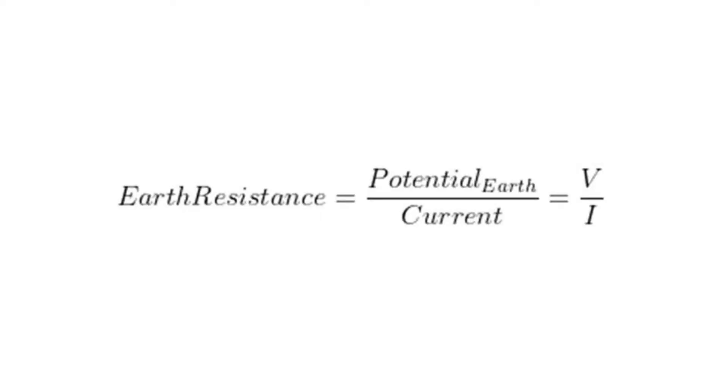When we talk about Earth resistance, we mean the resistance of the Earth electrode where the current flows into the ground. The Earth electrode is not a single point, as the resistance is distributed over the soil surrounding that point where the current flows.